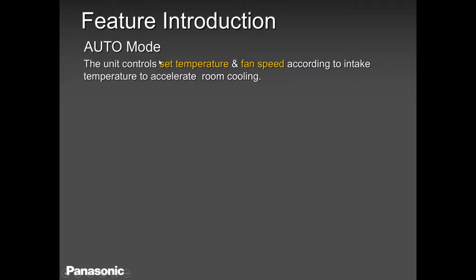But to me, as a technician, I have noticed auto mode is just a waste of energy, because for two hours you're heating the space, the next 2 hours you're cooling the space, and the next 2 hours again you're heating the space. So you're fighting against each other, cool against heat. In my opinion, based on my experience, auto mode is very rare. But again, it's there, you can use it.